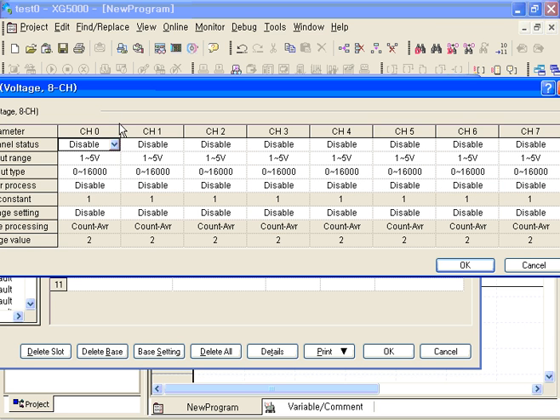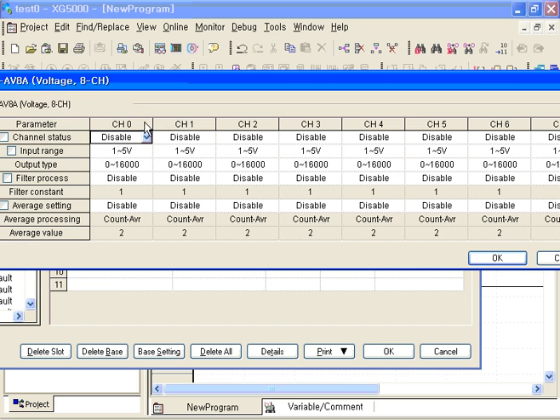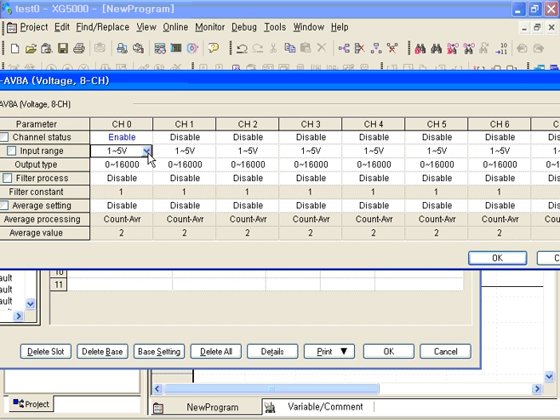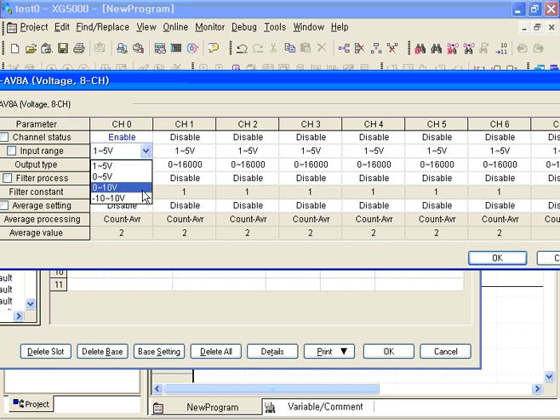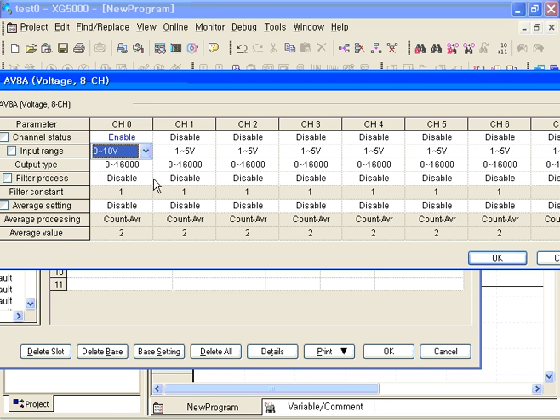Channel enable - for example I will use channel 0. Enable input range, I select 0 to 10 volts for example, and the range is 0 to 16000. So if 5 volts is applied, the value would be 8000, just half.